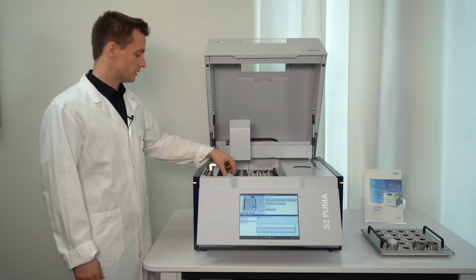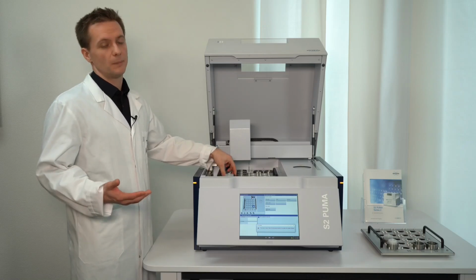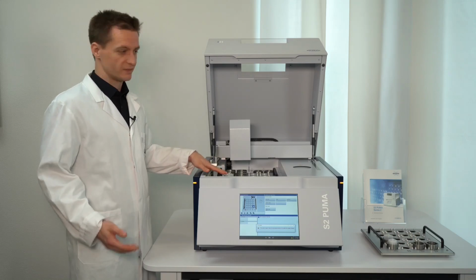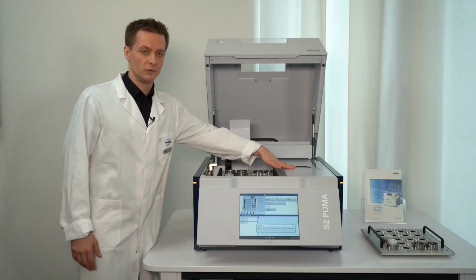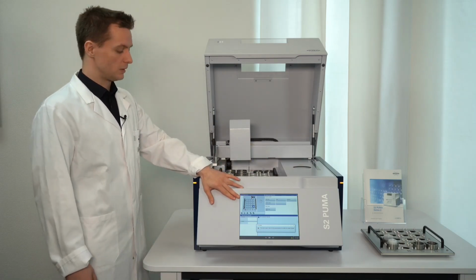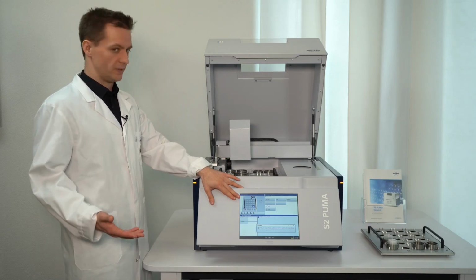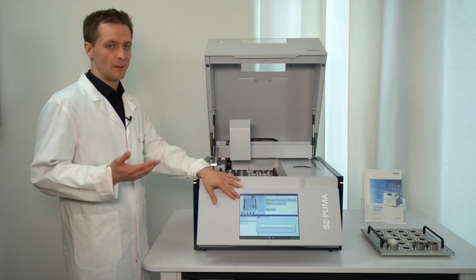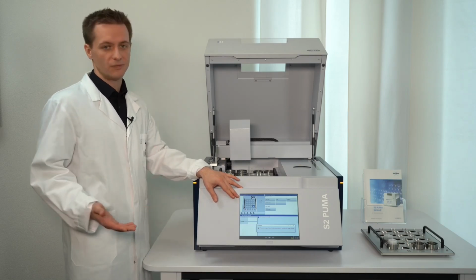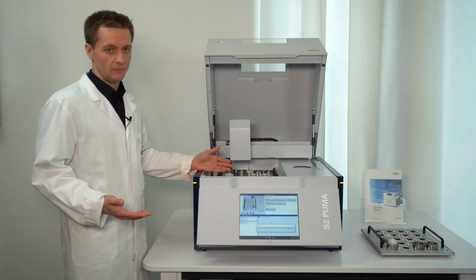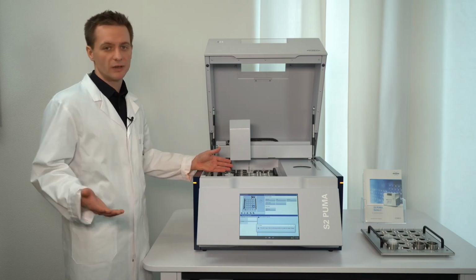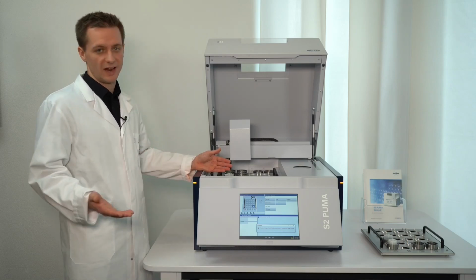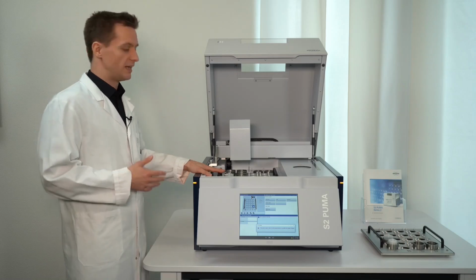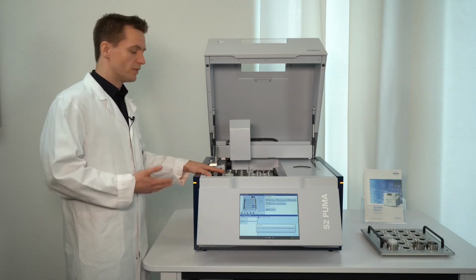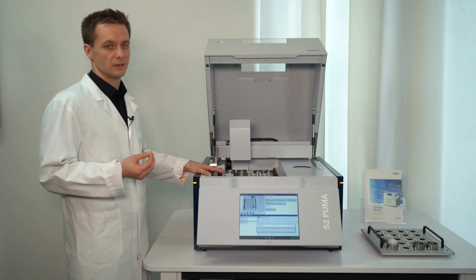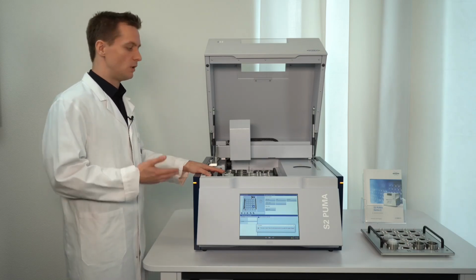The 20 position tray here holds the steel rings, which can facilitate powder samples, solids, pressed pellets, as well as liquids. The grabber will load these cups over here into the sample chamber, and operators can run the whole system via touch control with a simple press of a button. And this is actually the ideal setup for any type of process control or production control, because you have the maximum flexibility. You can have different types of samples in one run with different atmosphere modes, and the operators do not have to think about which sample needs to come first, or wait until an analysis is done, because loading and unloading of samples can happen at any time, even while an analysis is running, without any interference. So this really provides high flexibility, and people have to spend minimum time on actually running the analysis.